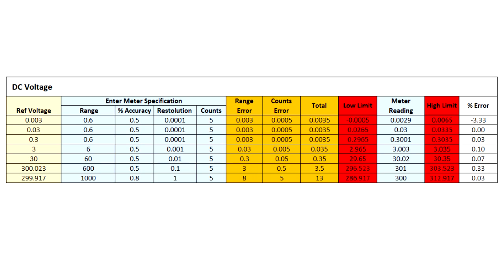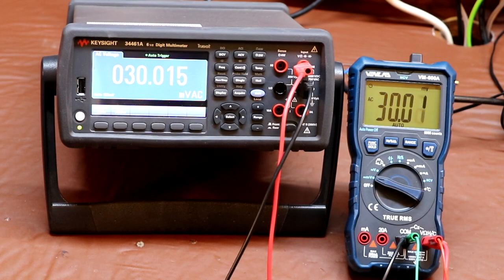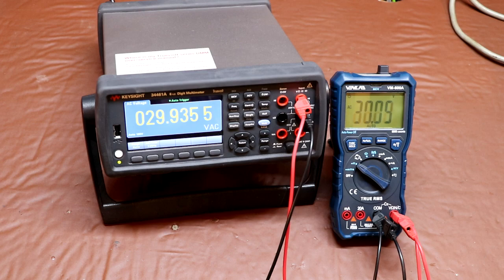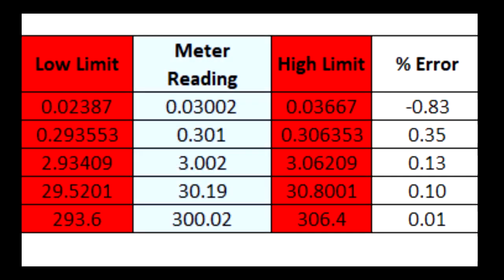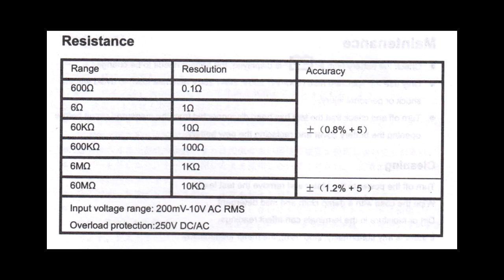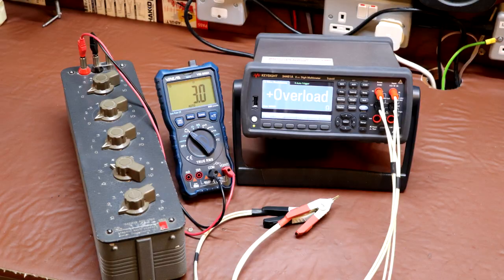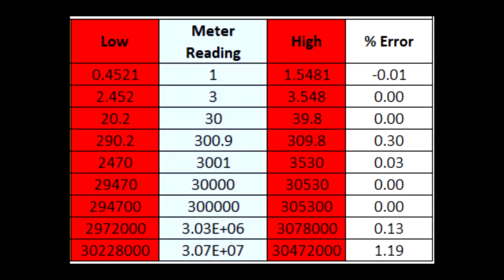And using my internal temperature calibrator it does appear that the thermocouple is also quite accurate. Our DC voltage range far exceeds specification. I was able to test the VM600 up to 300 AC volts and it was very accurate on all ranges. Taking readings at 10 hertz and 1000 hertz the meter comfortably exceeds the specified frequency range and the meter was 3dbs down at 2085 hertz. I checked all six of the meter's resistance ranges between 1 ohm and 30 megaohm and again I found the meter exceedingly accurate.